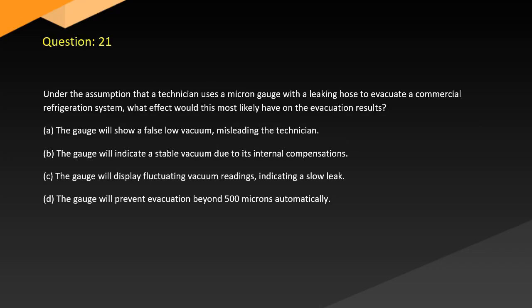Question 21. Under the assumption that a technician uses a micron gauge with a leaking hose to evacuate a commercial refrigeration system, what effect would this most likely have on the evacuation results? A. The gauge will show a false low vacuum, misleading the technician. B. The gauge will indicate a stable vacuum due to its internal compensations. C. The gauge will display fluctuating vacuum readings indicating a slow leak. D. The gauge will prevent evacuation beyond 500 microns automatically.